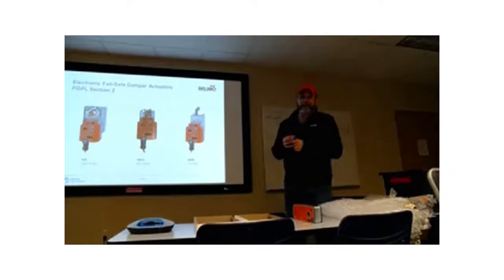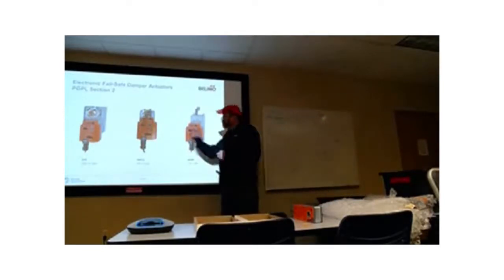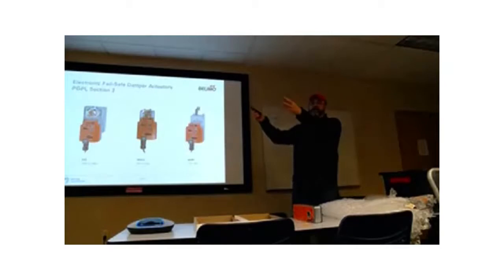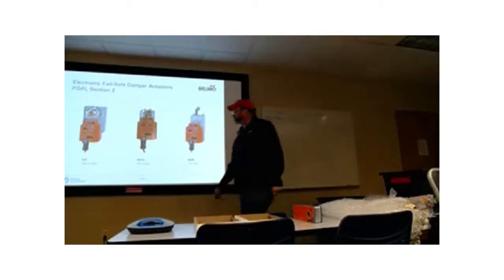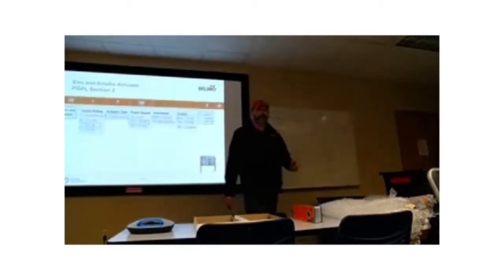These are 4-second actuators. You can potentially use them for makeup air, like fast acting makeup air, or things like that. You just have to look at the application. But we use them on dual duct boxes. That's an older technology where you have hot air and cold air that go out to the terminal and mix them in the terminal unit. Seattle doesn't like them very much, but there's still a few around. So we have that, and that's also electronic failsafe.